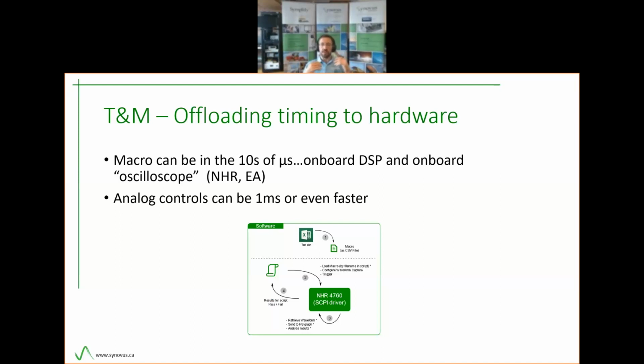So let's start with the macros and the profiles. You can see on the slide generally how it works. You load something in the instrument, and then you ask the instrument to do it. So once you have programmed the various voltages, currents, slew rates, limits sometimes to be done at given time intervals, your test control software can execute them with a single command or even a digital trigger.